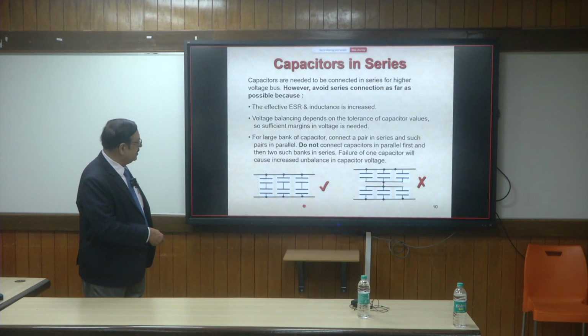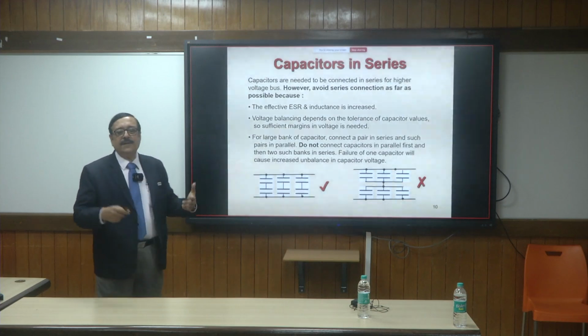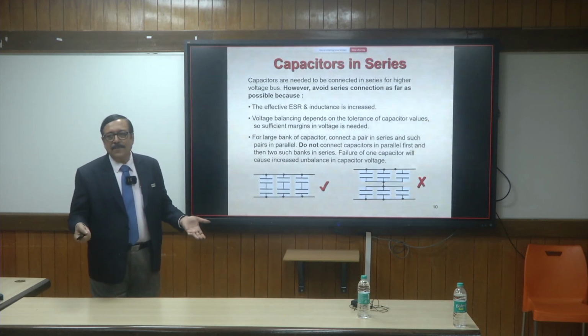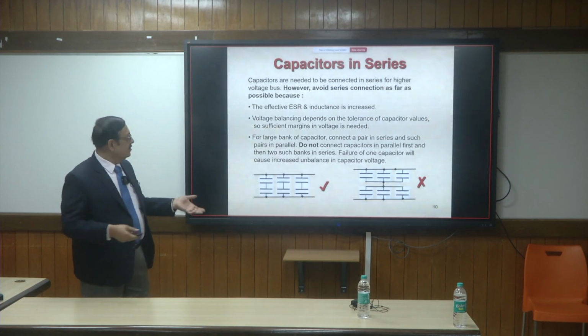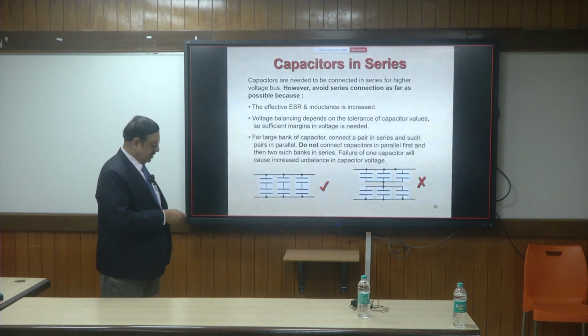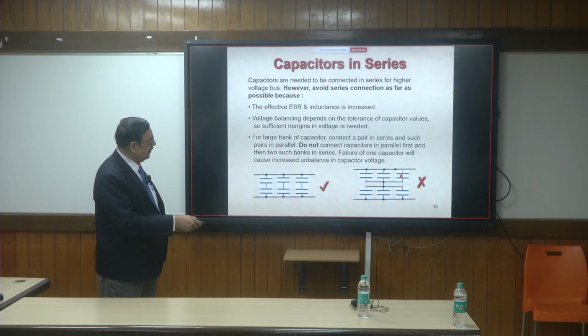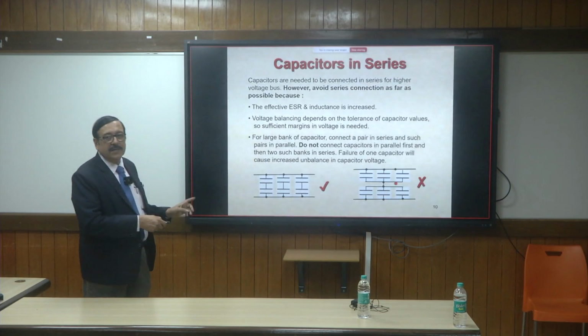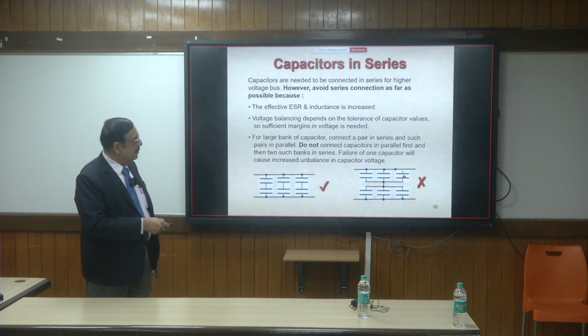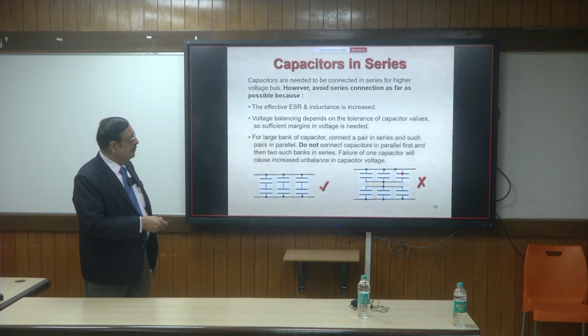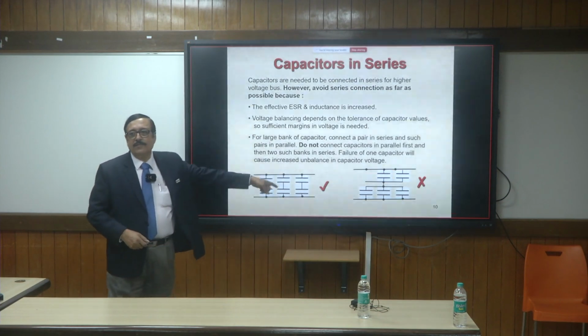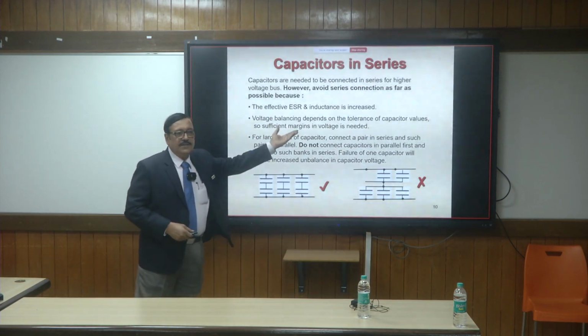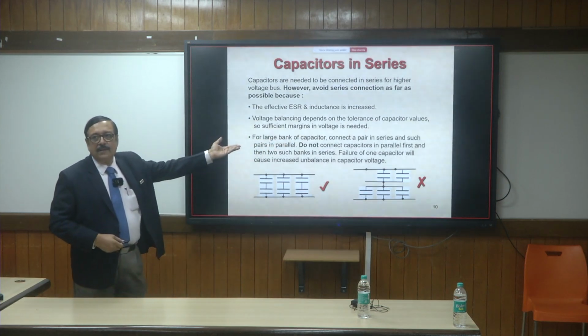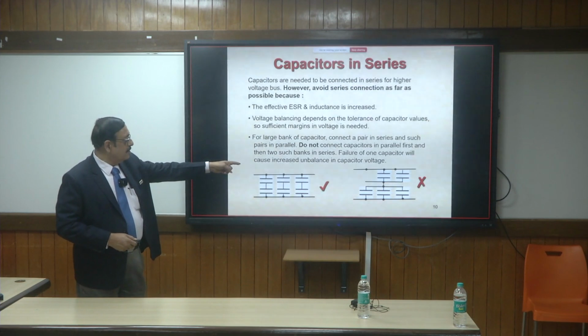You put the capacitors in series and then put them in parallel across the bus. Why parallel? Because when you put them in series, the effective capacitance becomes half. So you have to compensate for the need of total microfarad by putting parallel branches. But if you parallel the capacitors first and then put the two banks in series, you are making a mistake. Because if one of the capacitors in that bank blows out for some reason, you will have a huge unbalance. You can see now you have two capacitors on the top and three at the bottom. So the midpoint voltage will shift drastically and you will have a cascaded failure of all the other capacitors. So that type of connection should not be done in the middle.